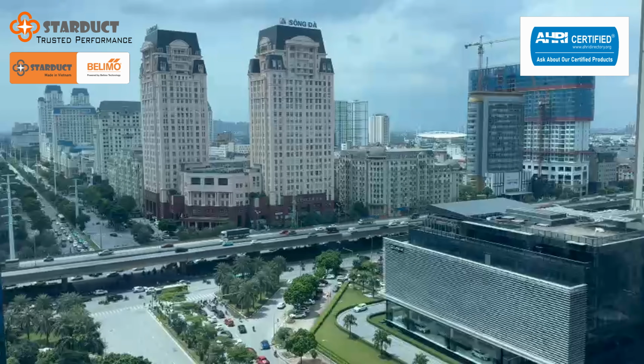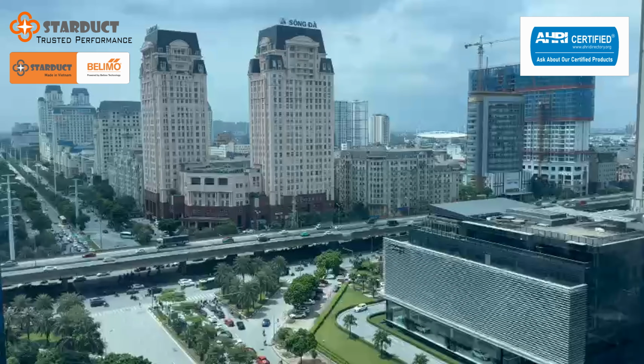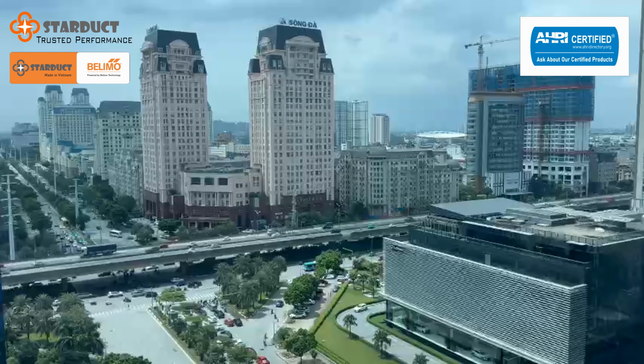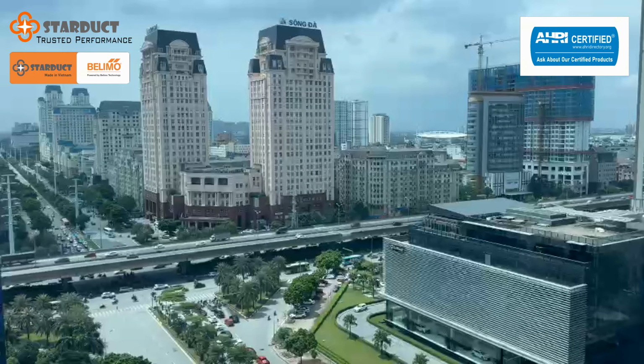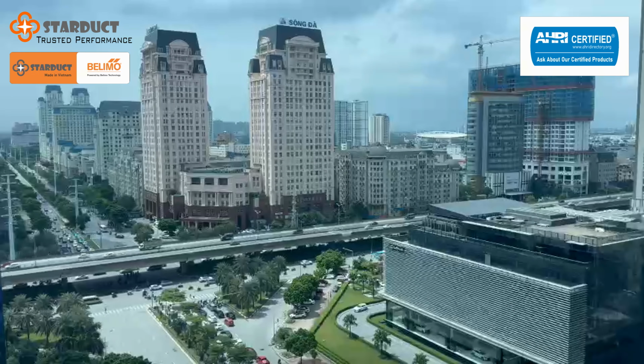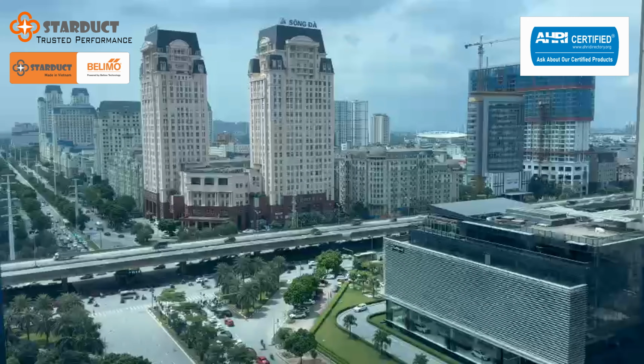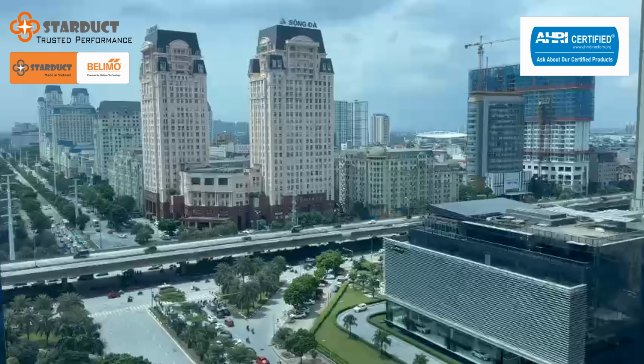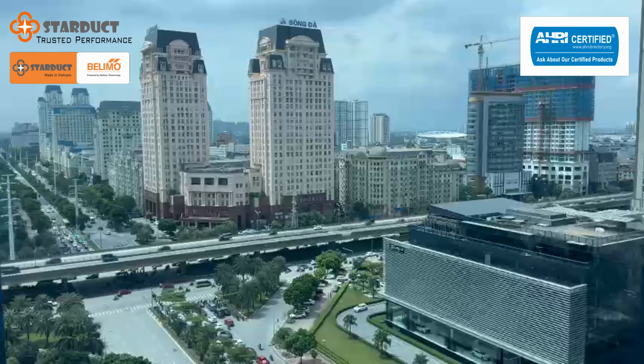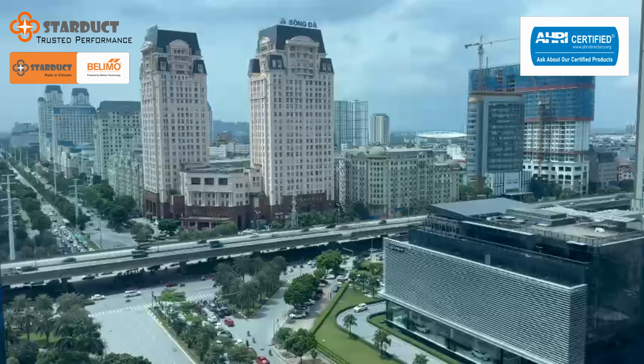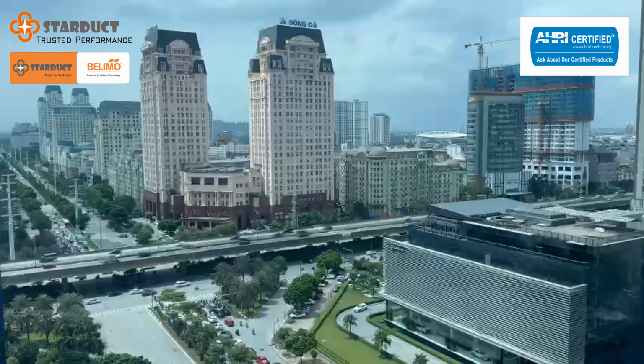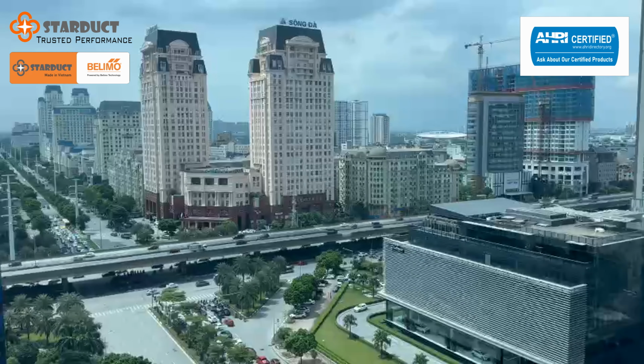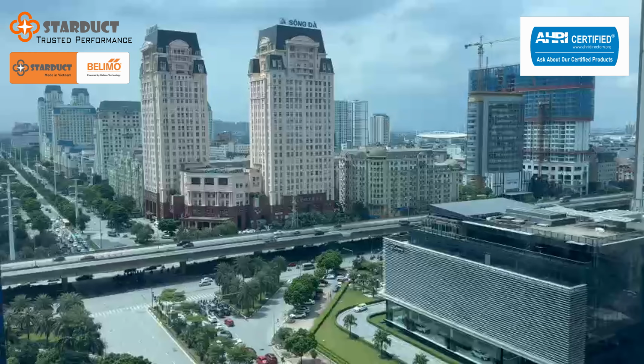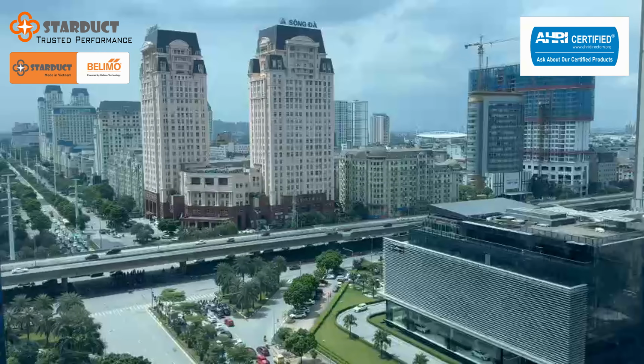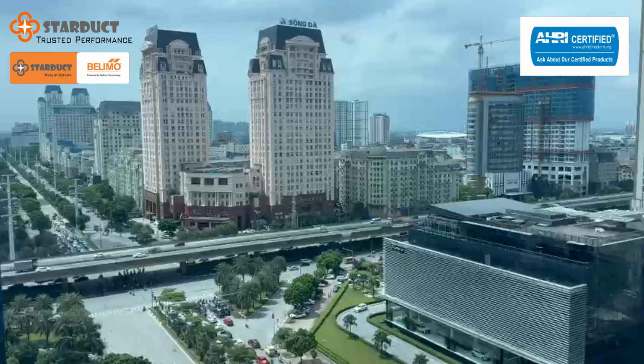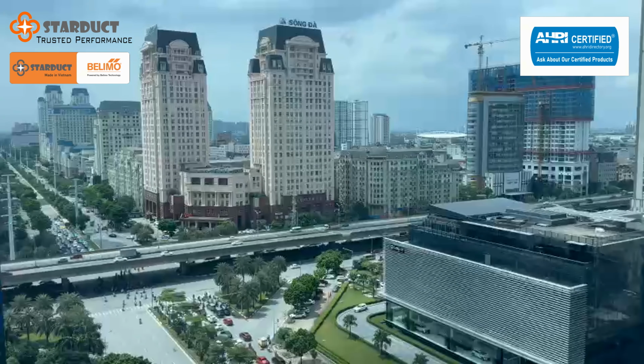These are calculated using standardized tests, often under specific conditions, like 1.5 inches water gauge, and based on certified data. And the engineering itself, the physical product, implies a certain level of trust. We're talking about highly corrosion-resistant materials like the ZnAlMg body, dampers with EPDM seals, ensuring leakage is minimal, less than 0.5%, even at high pressure. This inherent quality means that theoretical K value should be reliable.